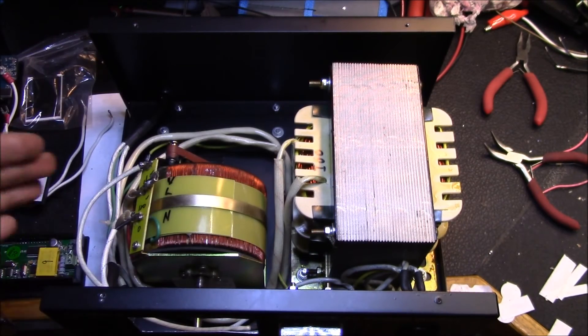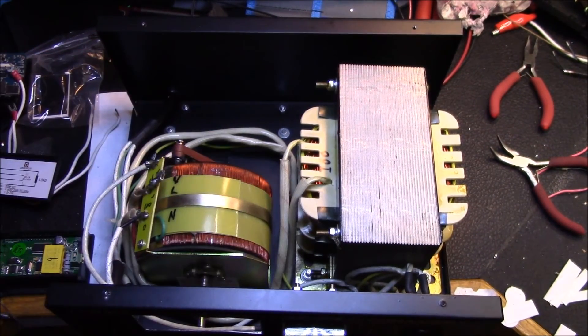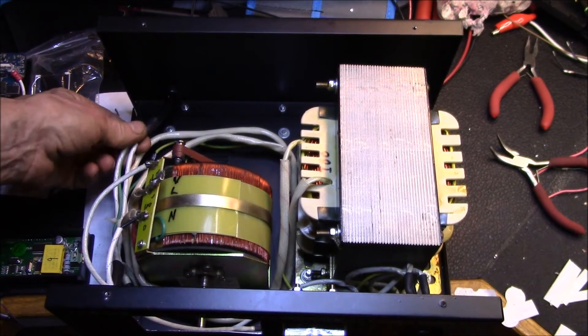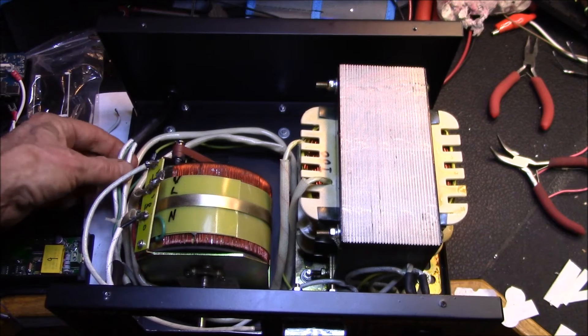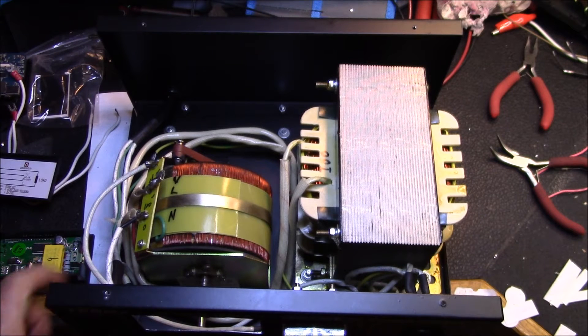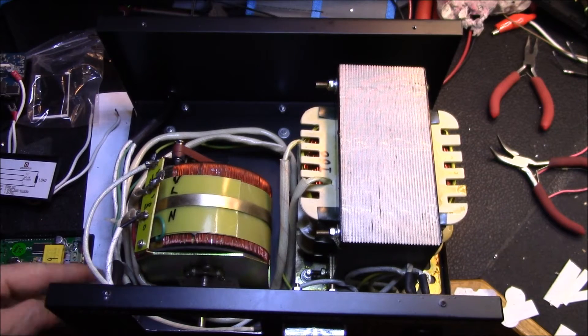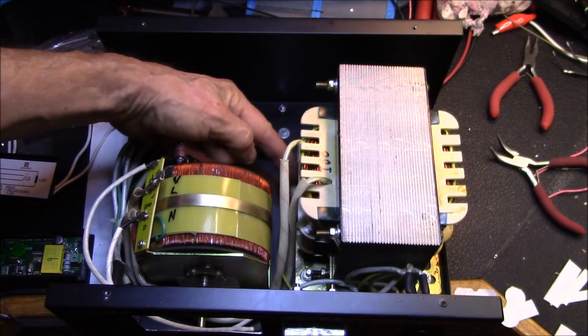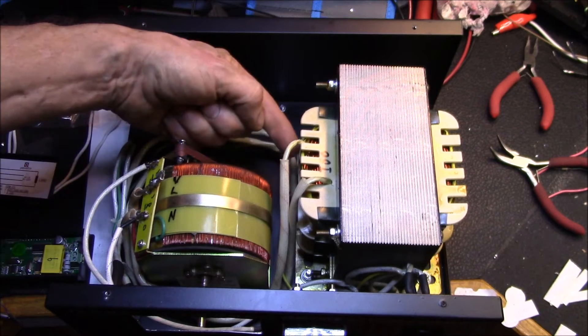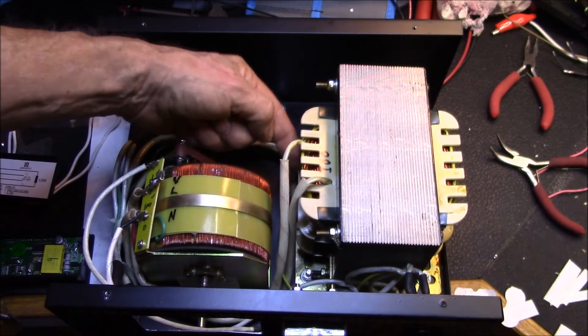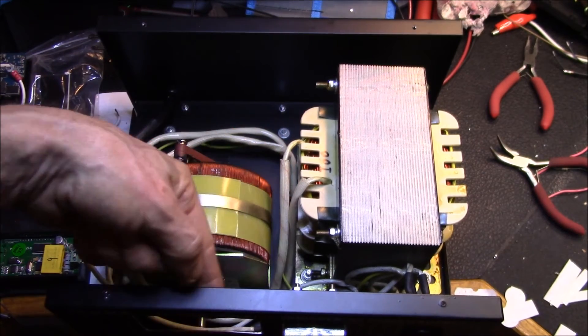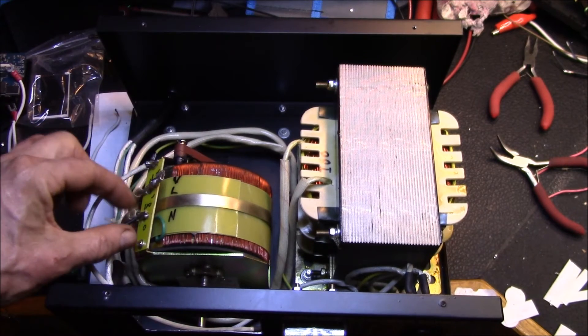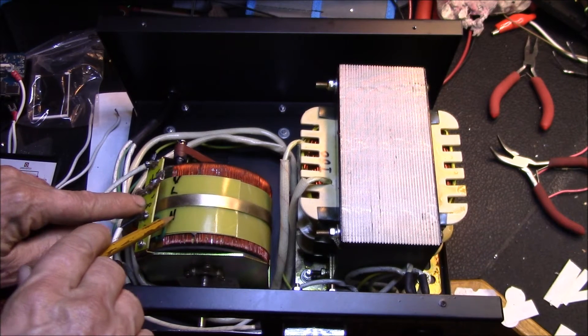The other thing that matters is what is line and neutral inside of this power supply and how is it wired. Here's your incoming power cord, your green earth or ground wire, and then the line and neutral come in. Down here there's a fuse, so the line goes through the fuse, then down at the bottom there's a double-pole switch. Those wires run over to the isolation transformer. There's the 120 volt winding down here, and then there's an isolated, with a plastic insulator, separate 120 volt winding up here. These are the isolated line and neutral connections that come over here to your variac.